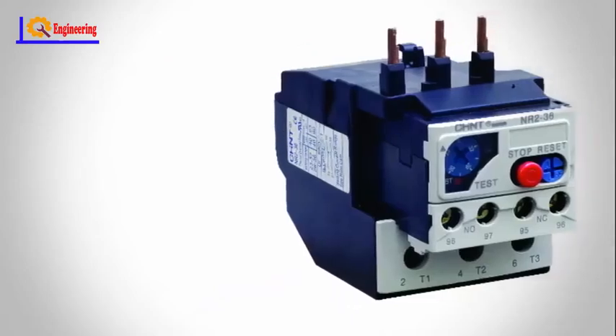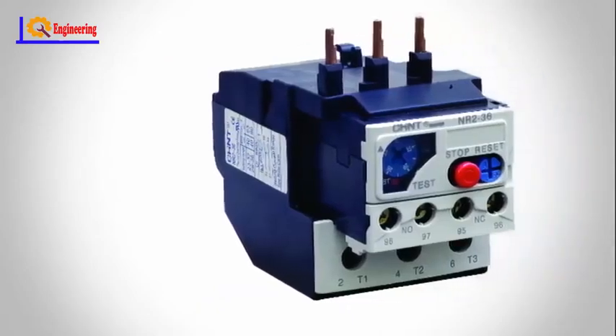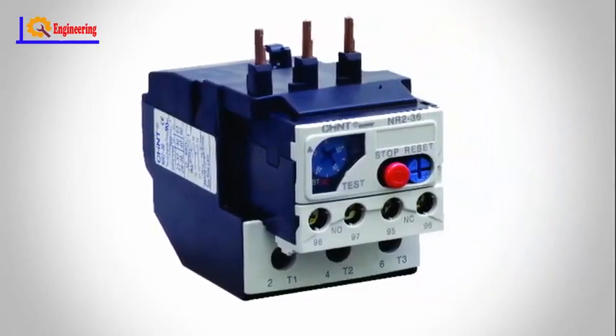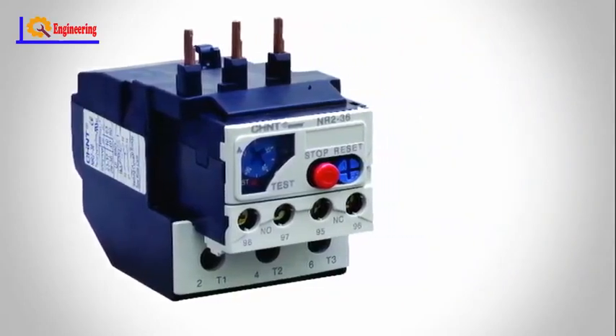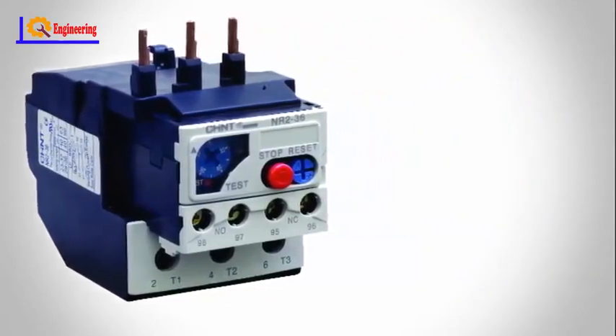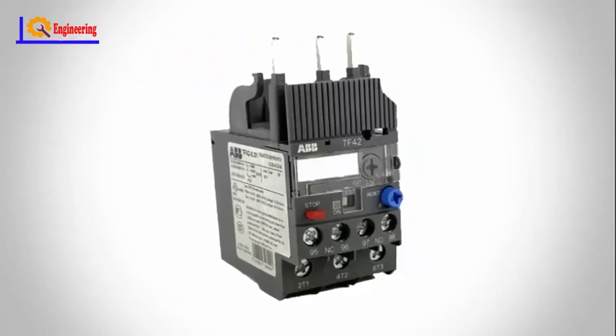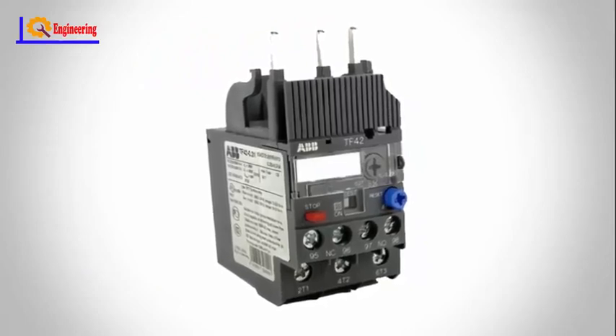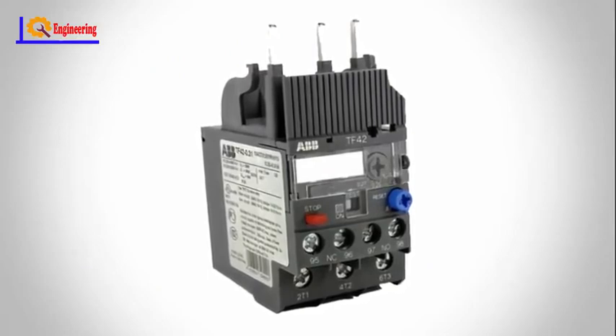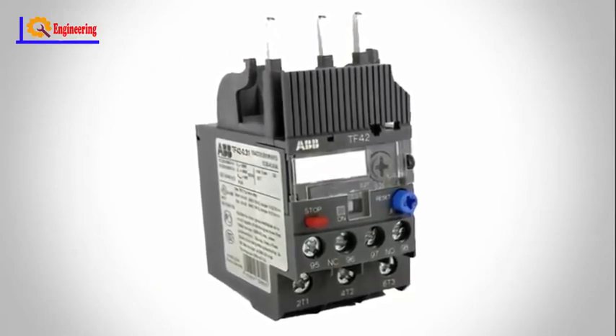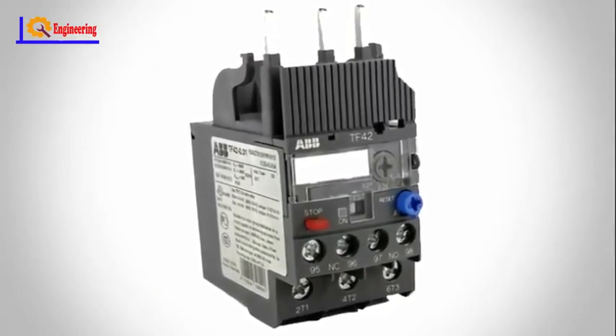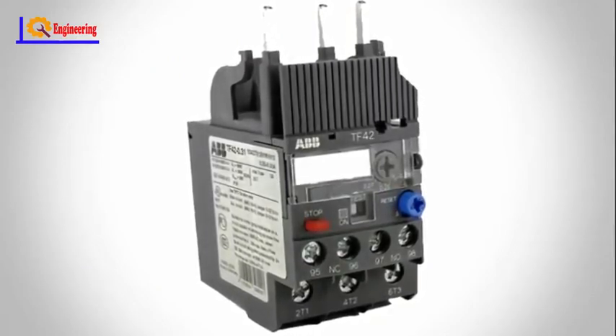Thermal relay. These relays are based on the effects of heat, which means a rise in the ambient temperature above the limit directs the contacts to switch from one position to another. These are mainly used in motor protection and consist of bimetallic elements like temperature sensors as well as control elements. Thermal overload relays are the best examples of these relays.